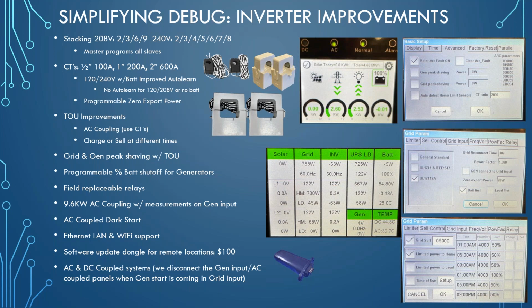We have field replaceable parts. The field replaceable relays are really handy. Those are on the grid side. And then, of course, we have the 9.6 AC coupling. Quick note on that: we can AC couple on the load side, meaning the load breaker, or the gen side, meaning the generator breaker.